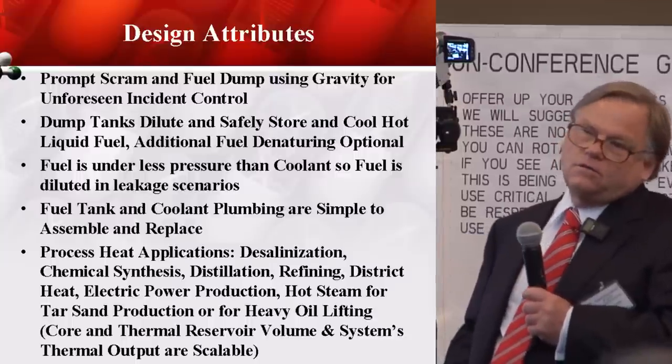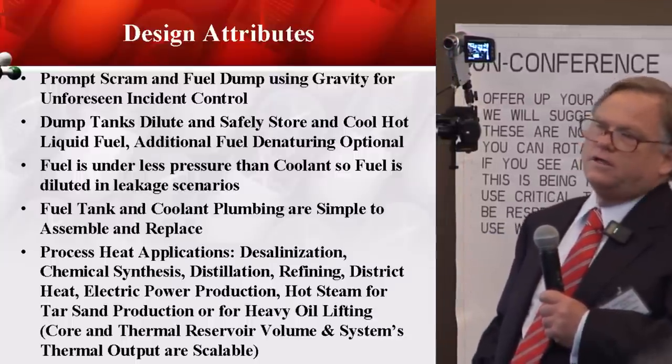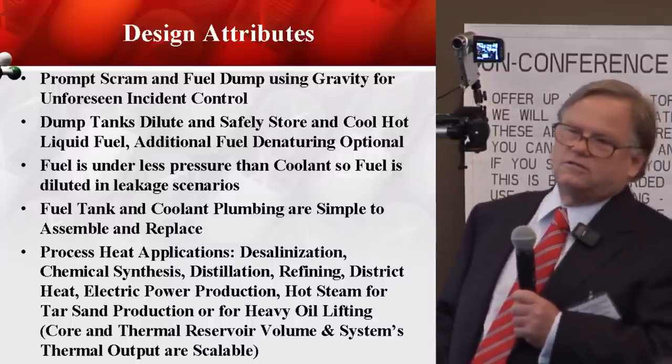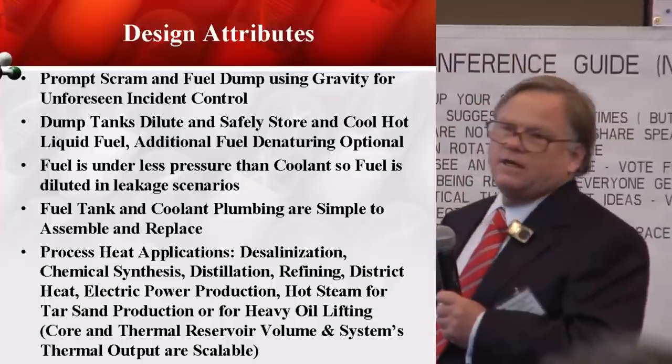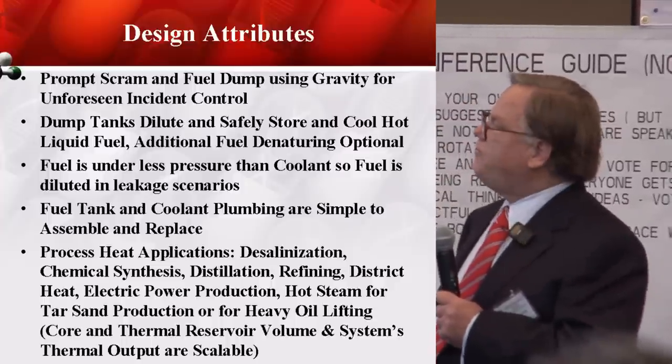The design attributes: we have the prompt scram. We have the fuel under less pressure than the coolant, and we're just talking a couple of PSI. This way, the bias is towards diluting the fuel, so as the fuel becomes more dilute, the chain reaction will cease automatically and passively in the event of leakage or mechanical failure. This design is relatively simple to construct.